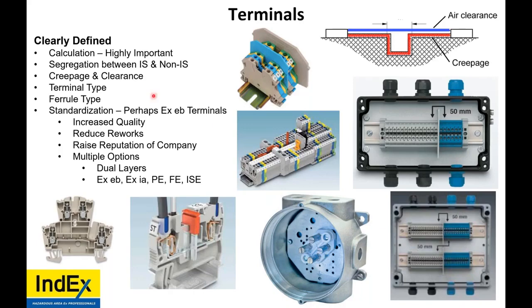So we have to do a calculation. It's highly important how many terminals we can use: the segregation between IS and non-IS, our creepage and clearance distances, our terminal type, our ferrule type, also standardization, perhaps Ex eb terminals. If a manufacturer, vendor, or EPC always called for an Ex eb terminal, they would have increased quality in their works and reduced reworks, because when you have the two types of terminals on the shelf, the person selecting many times selects the wrong one. And as we do inspections, then you're going to have a lot of reworks.